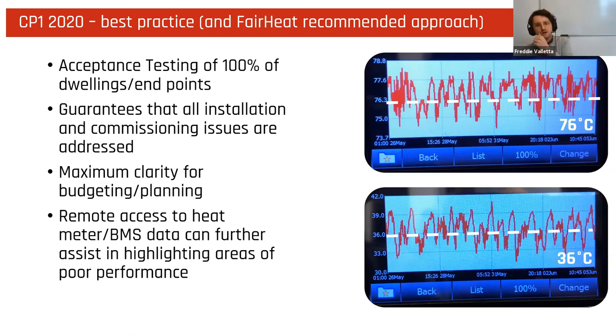pre-occupation. Whilst you may be thinking that 100% of testing seems a bit overkill and could impact on project timelines, it's actually the best approach to take, not just in terms of the results that it produces, but in terms of being able to budget and plan for this commissioning and testing phase of the works without any unknowns. The 10% plus 10% minimum requirement approach stipulates that if any of those fail, a whole new set of 10% has to be tested and passed in order to prove correct commissioning. And then another 10% if any fail, another 10% if any of those fail, and so on. This introduces quite a lot of unknowns into project planning and budgeting.